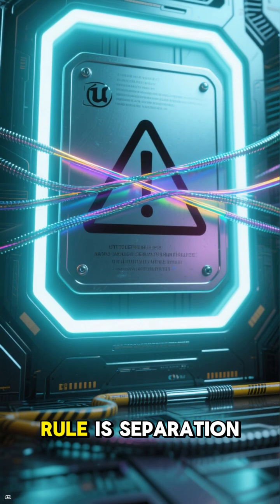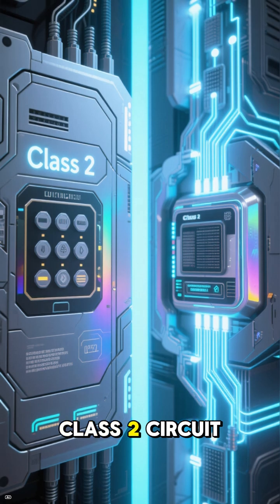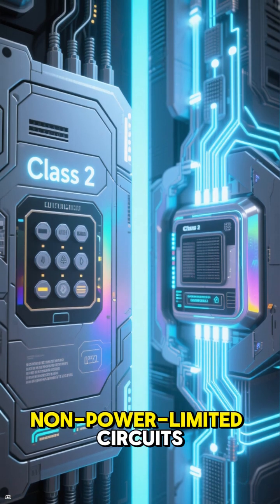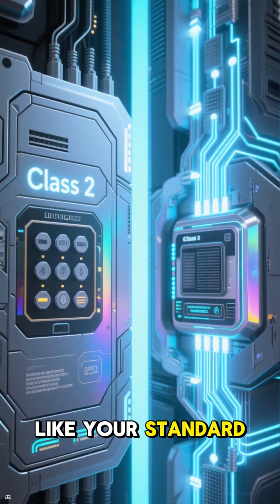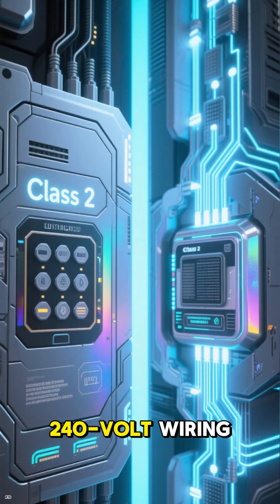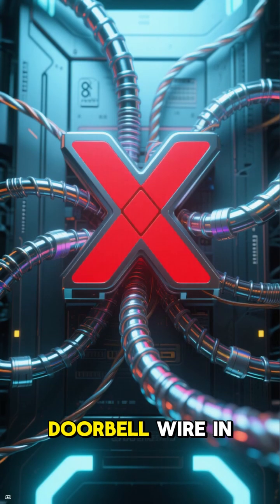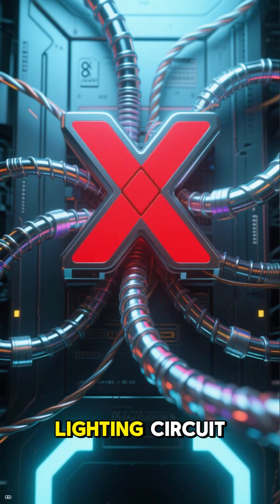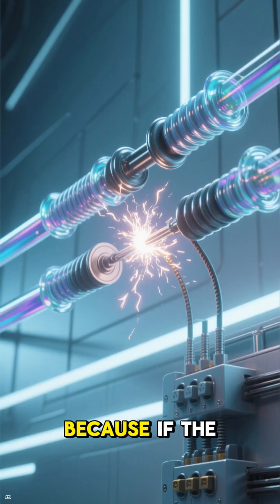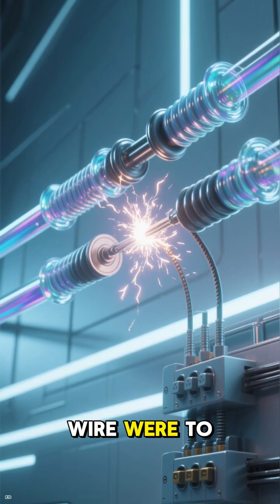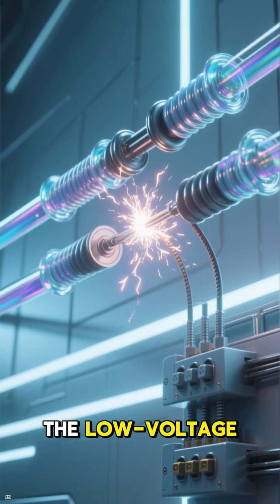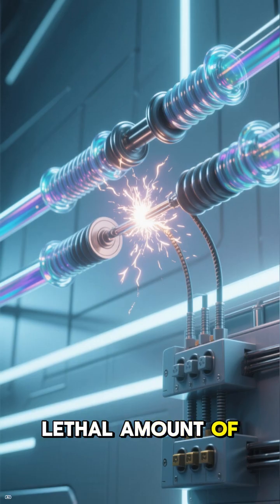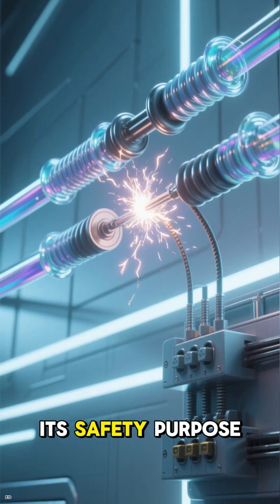The most critical rule is separation. Class 2 circuit wiring must be kept separate from non-power limited circuits, like your standard 120-volt or 240-volt wiring. You can't just run your doorbell wire in the same conduit as your lighting circuit. Why? Because if the insulation on the high-voltage wire were to fail, it could energize the low-voltage Class 2 circuit with a lethal amount of power, completely defeating its safety purpose.